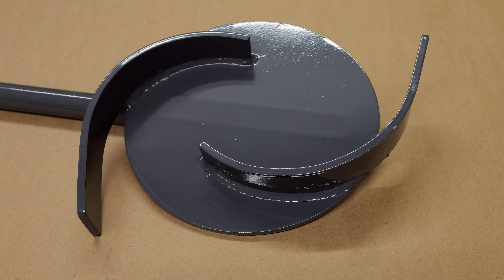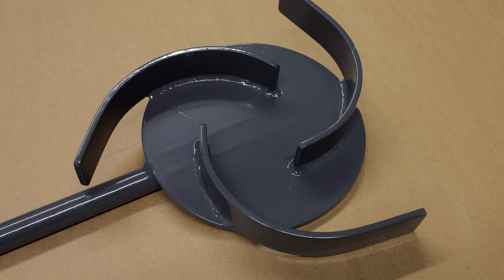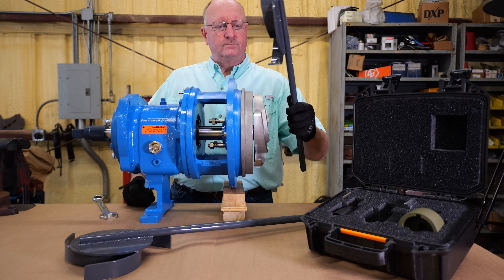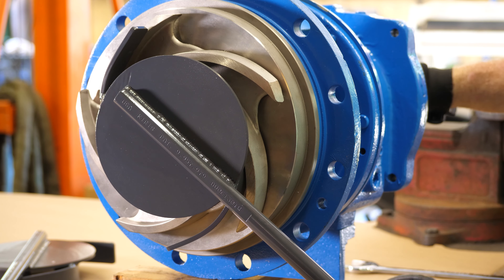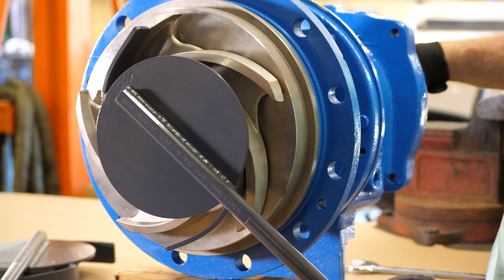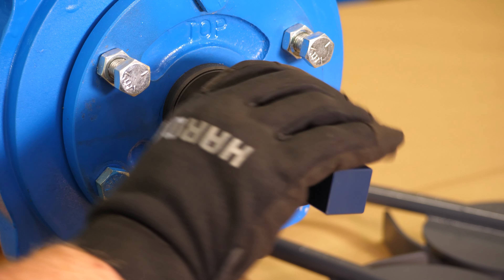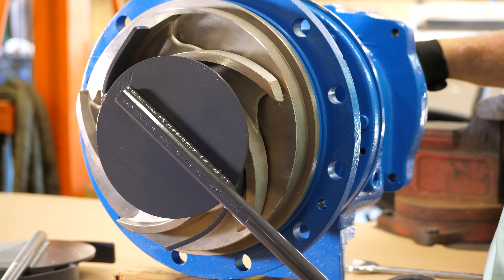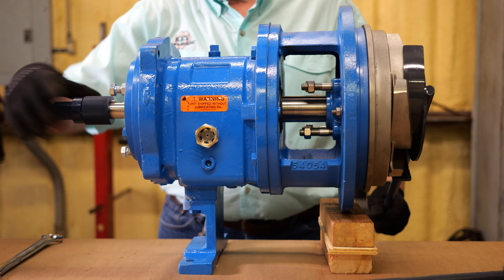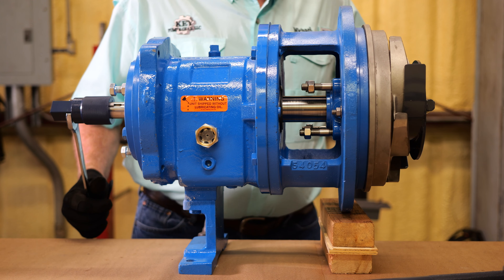Now you'll choose the impeller wrench that's right for your job — either the one with an odd number of vanes or the one with an even number of vanes. Line the wrench up with the impeller; using the impeller wrench protects your hands from coming in contact with sharp edges. Using your other hand, grab the knurled section of the drive end socket and lightly turn the socket to ensure all vanes are engaged.